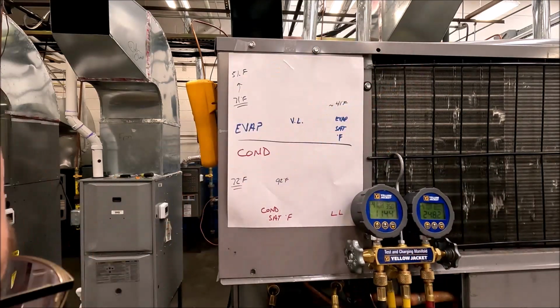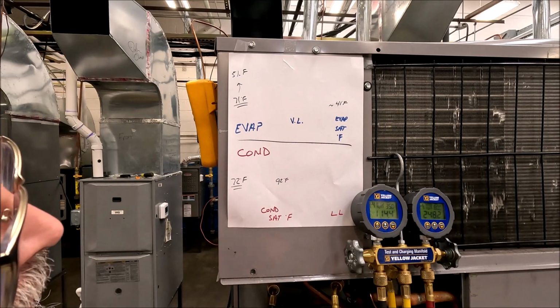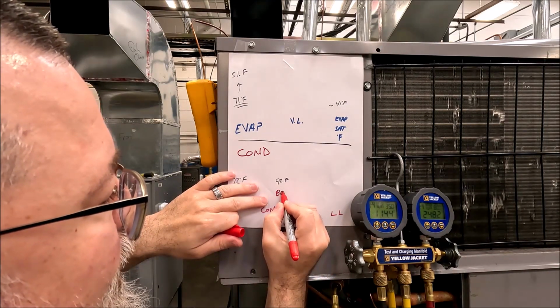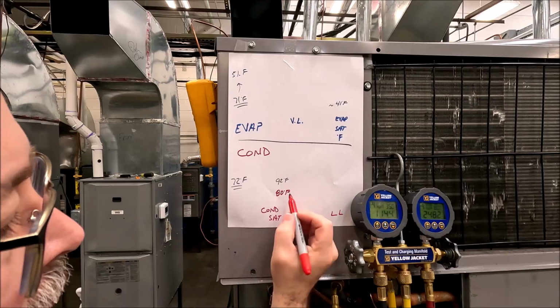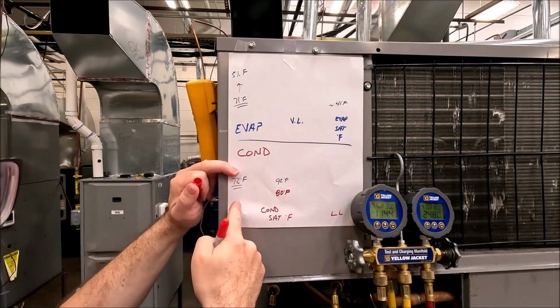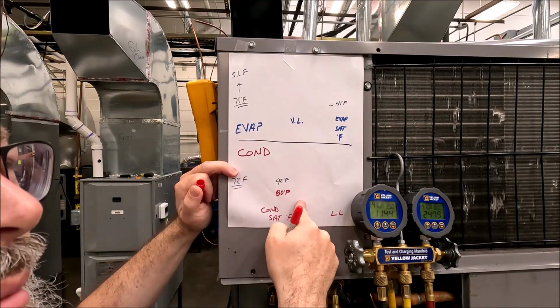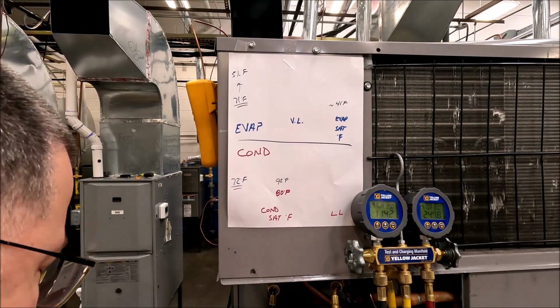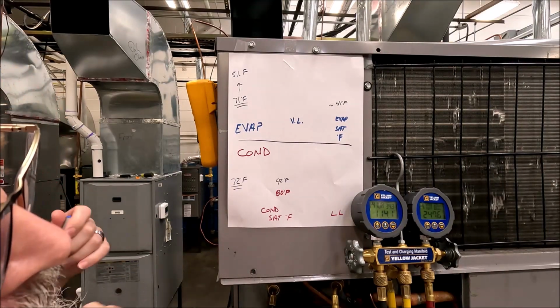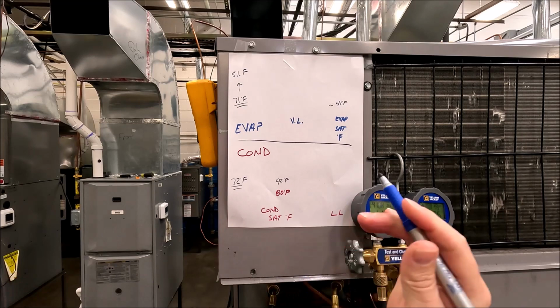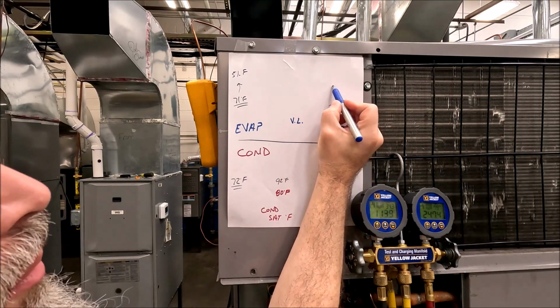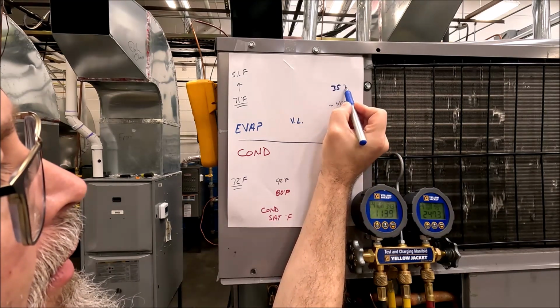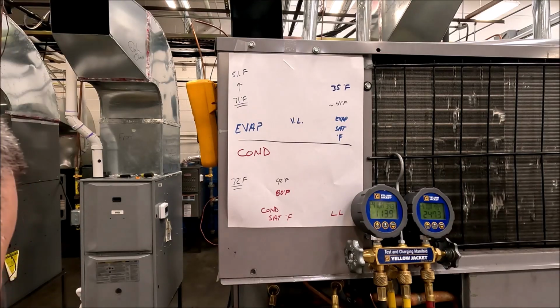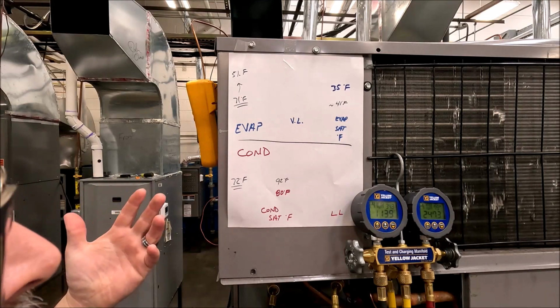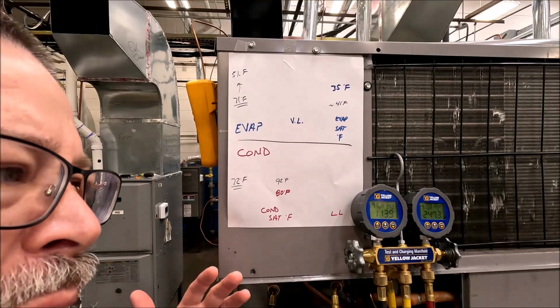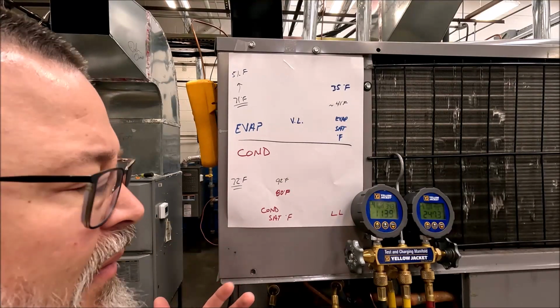So if I fill in that number here, I'm 80 degrees on my saturation point. I'm still higher than the 72, but I'm not where I thought I would be. For my evaporator saturation temperature, it's actually fluctuating a little bit. I'm at my 35 degree point. All right, so maybe they both look a little low.